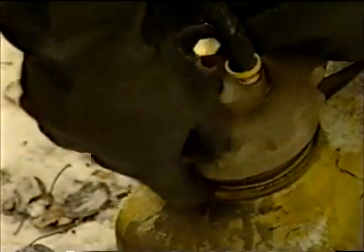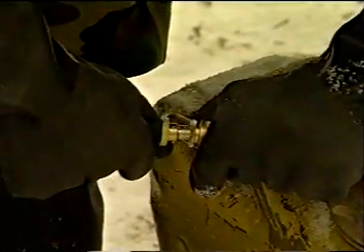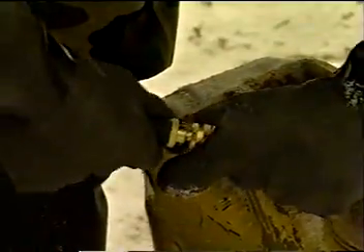After ensuring the fuel on-off control on the fuel flow control valve is set to the off position, remove the cap from the mouth of the fuel can and replace it with the gravity feed adapter. Thread the adapter onto the fuel can securely to prevent fuel leakage. Attach the male end of the fuel supply hose to the gravity feed adapter fitting and set the assembled fuel can aside.